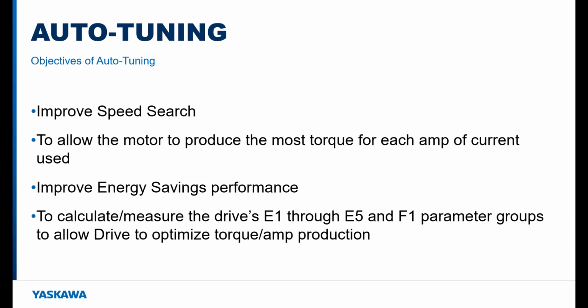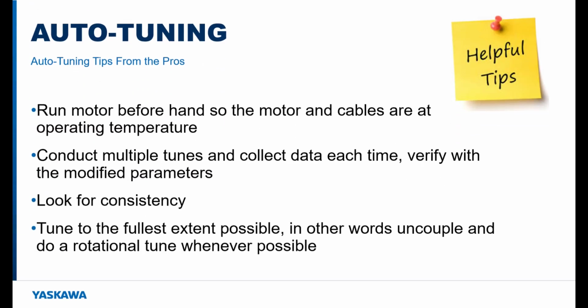When is the best time to auto-tune? You'll want to usually do this after the motor's been warmed up. Maybe let it run for an hour. And when you're doing auto-tuning, you want to do it multiple times till you find the values start to become consistent. And we'll start with the standard or rotational auto-tuning.